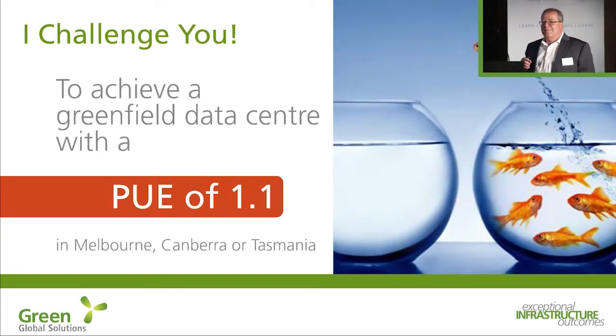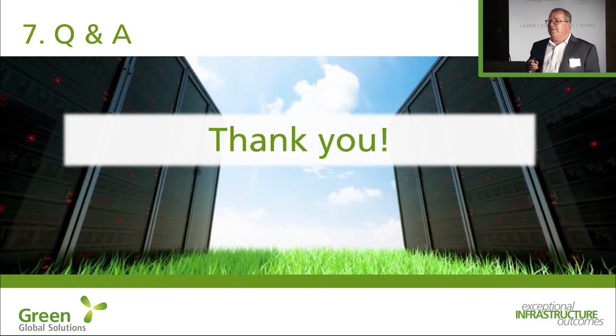Okay, this is a little challenge: to achieve a data centre with a PUE of 1.1. Some people are scratching their heads saying, can it really be done in Australia? Well, I say it can be done, but it's going to be done the right way. And no, it can't be done in Darwin. No, it can't be done in the warmer states, not that kind of PUE. But like I said, in a place like Melbourne with a relatively cooler climate, a PUE of 1.1 and breaking the 1.1 barrier is quite feasible. Canberra, I believe we can go down to 1.07. They've got the best cooling hours in Australia, more so than Tasmania, which surprised me when I checked the numbers, but they do. So there's a challenge. Now, what I'd like to do at this point is open the floor to questions.